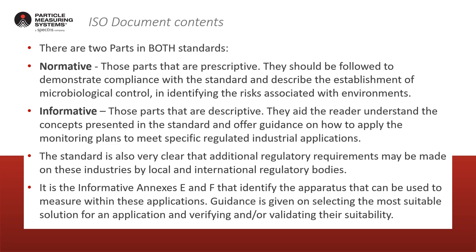Then there's also the informative component — those parts that are descriptive and meant to aid a reader's understanding of the concepts presented in the standard, providing guidance on how to apply the monitoring plans to meet specific regulated industry applications. The standard is quite clear that additional regulatory requirements may be made by local and international regulatory bodies. It's essentially a framework around which GMP can be managed. The informative annexes identify the apparatus that can be used to measure within these applications, and guidance is given on selecting suitable solutions and verifying or validating their suitability.